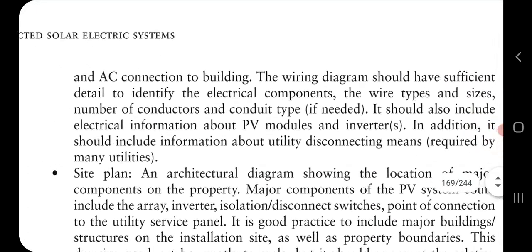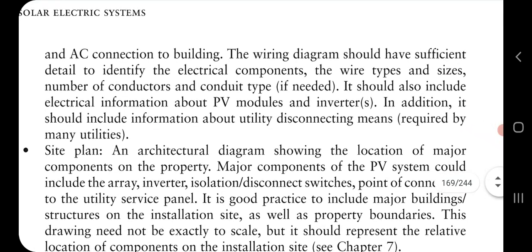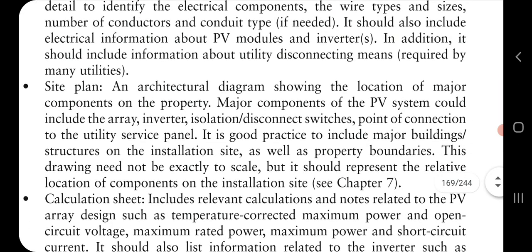First, the wiring drawing should provide all the sufficient detail about the electric equipment and the size and number of the cables required, conduits, what the PV model is, what the inverter is, everything. A full detailed plan has to be given in this one. The site plan and architectural diagram have to be taken and checked properly, and the location of the inverter, isolators and arrays should be shown on the architectural drawing.